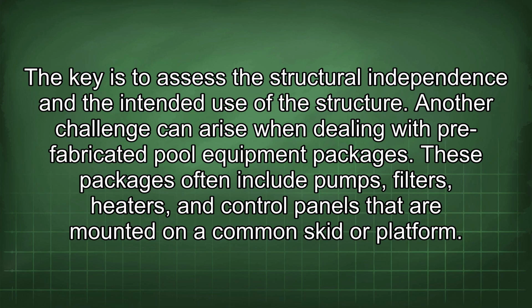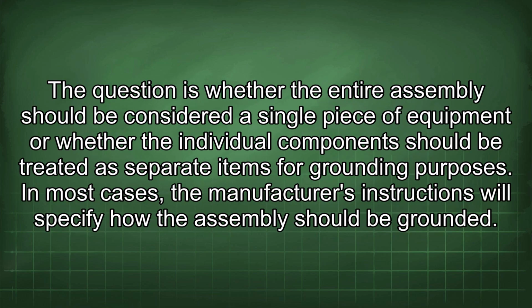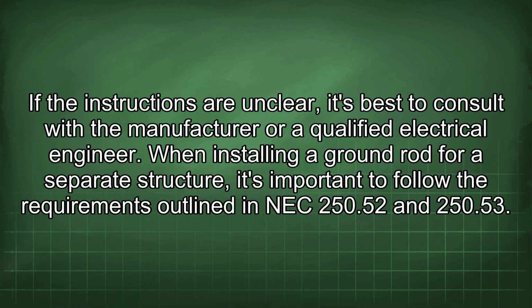Another challenge can arise when dealing with prefabricated pool equipment packages. These packages often include pumps, filters, heaters, and control panels that are mounted on a common skid or platform. The question is whether the entire assembly should be considered a single piece of equipment or whether the individual components should be treated as separate items for grounding purposes. In most cases, the manufacturer's instructions will specify how the assembly should be grounded. If the instructions are unclear, it's best to consult with a manufacturer or a qualified electrical engineer.